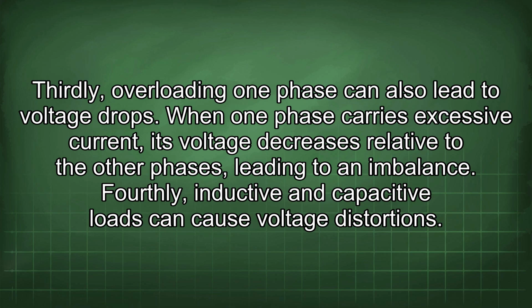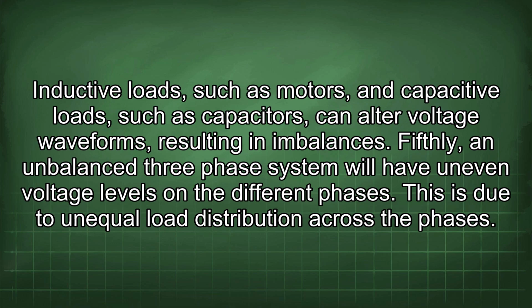Thirdly, overloading one phase can also lead to voltage drops. When one phase carries excessive current, its voltage decreases relative to the other phases, leading to an imbalance. Fourthly, inductive and capacitive loads can cause voltage distortions. Inductive loads, such as motors, and capacitive loads, such as capacitors, can alter voltage waveforms, resulting in imbalances. Fifthly, an unbalanced three-phase system will have uneven voltage levels on the different phases. This is due to unequal load distribution across the phases.